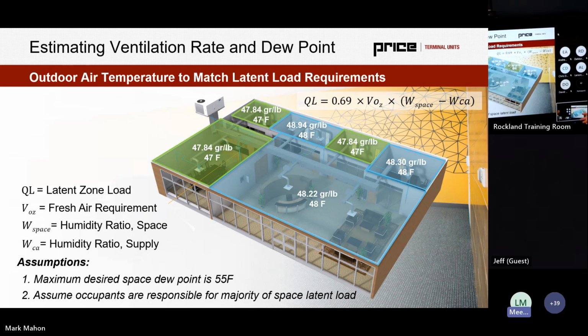Now, there's a few different approaches for this. Of course, we could dehumidify the air with desiccants. We could keep it at an elevated temperature. We could subcool it, reheat it, and deliver it at 55 degrees, not saturated and drier. But what we often see, especially in certain markets that we'll say are more shoulder season most of the time, like a Seattle market, is that they actually keep this air cooled to a 47-degree saturated supply air temperature instead. They use that as sensible cooling for the space, and on design day, that dries the space out as well. And this is all assuming a maximum desired space dew point of 55.